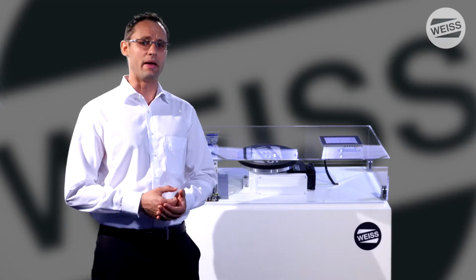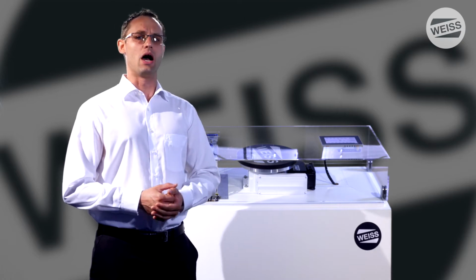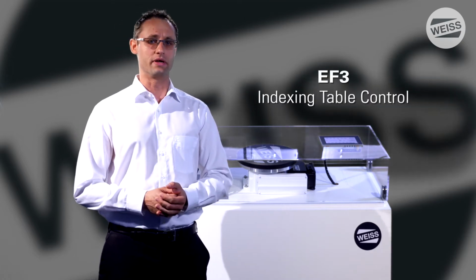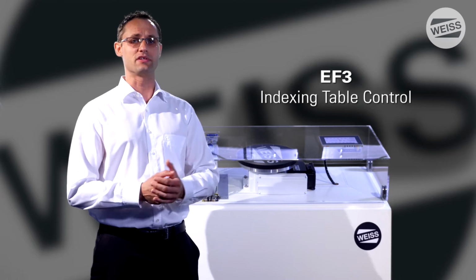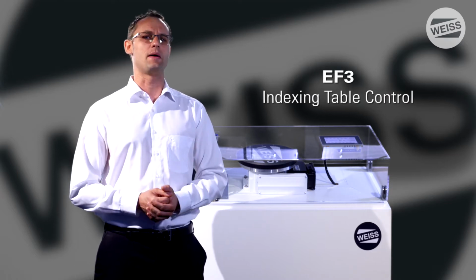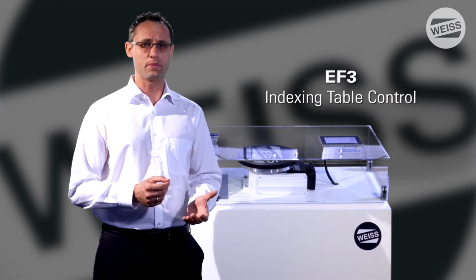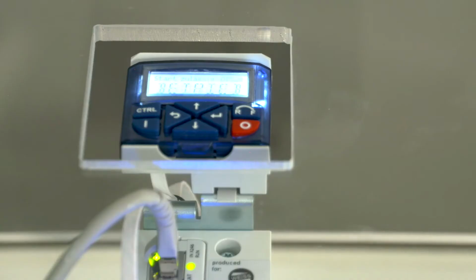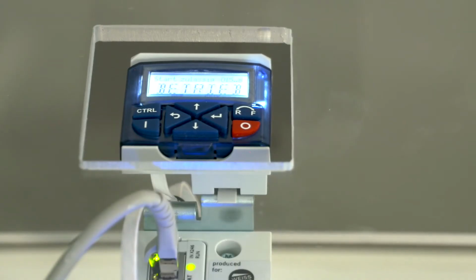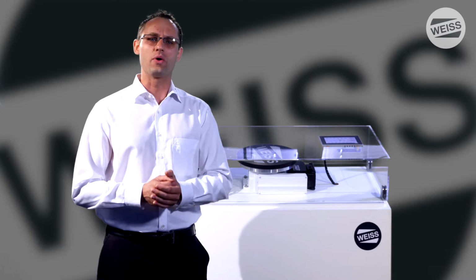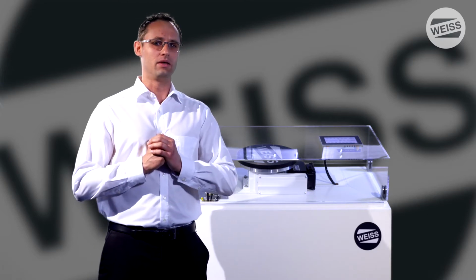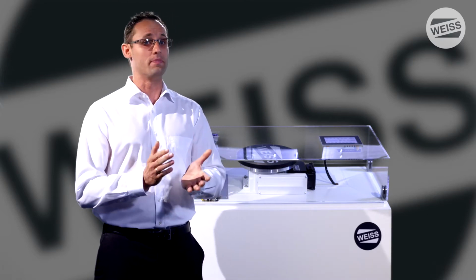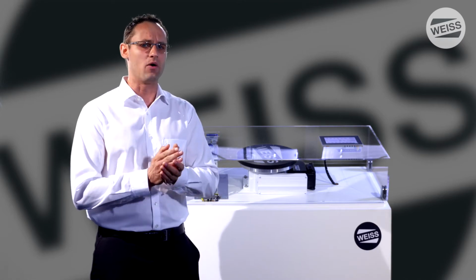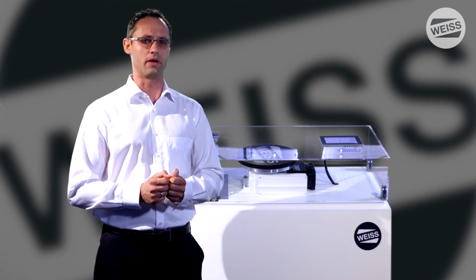Data collection is the basis of condition monitoring. Our dedicated indexing table controller EF3 samples relevant signals 1,000 times per second, makes some pre-processing and delivers valuable data for condition monitoring as a standard. We know our own rotary table very well and our controller, so our embedded firmware mines down there near the hardware the features we will need for powerful monitoring.